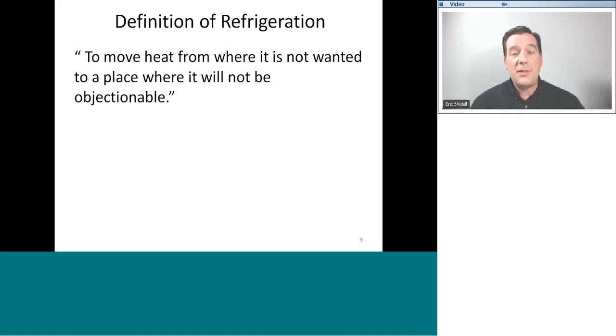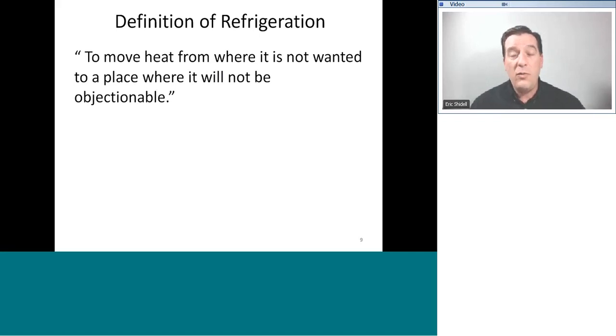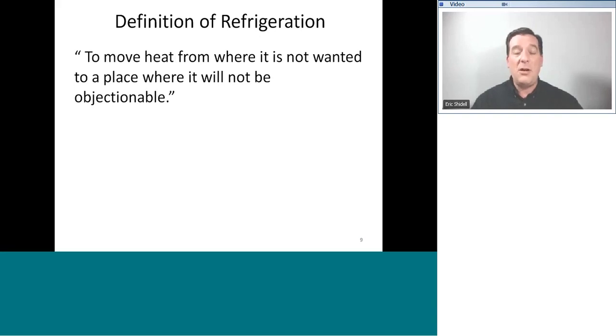We're going to do that by a process of refrigeration. The definition of refrigeration is to move heat from where it is not wanted to a place where it will not be objectionable — where we just don't care whether it's there or not. Notice I didn't say move heat from inside to outside, because that's not always what happens. Sometimes it could be moving heat from inside into a bucket of water, or in a water-cooled system depositing heat into the earth as in an earth-linked geothermal or geoexchange refrigeration system.